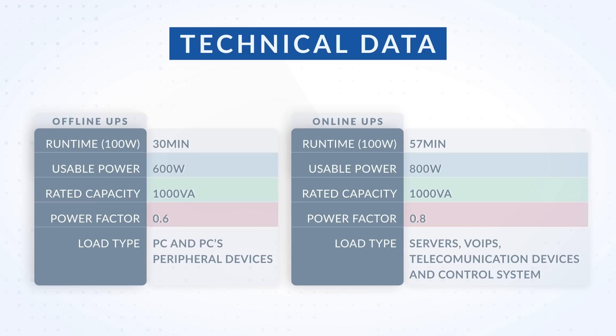UPSs are usually rated in volt-amperes. The higher the value, the more power it can output. To convert volt-amperes to watts, find the power factor of the UPS and multiply it by the volt-ampere value. With the known power consumption, you can determine how big the UPS has to be — meaning how much capacity it should have. More capacity means more time to finish your work.